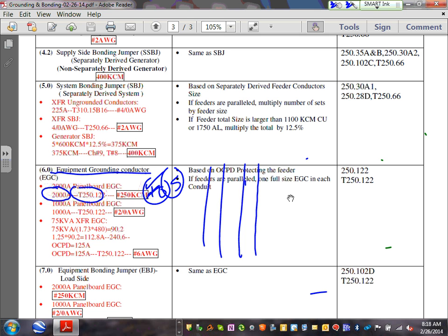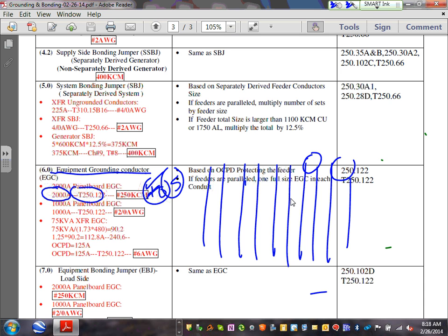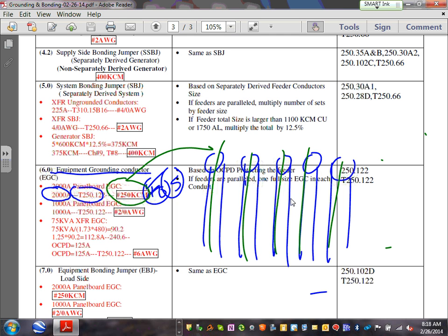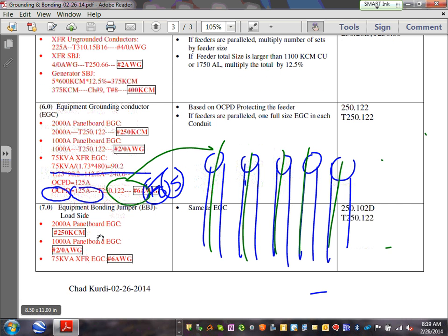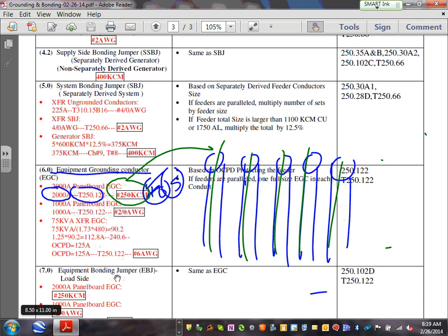Here's 1, 2, 3, 4, 5 conduits. All these are different conduits, and you will be pulling, gentlemen, 1, 2, 3, 4, 5 conductors, one in each and every one of these conduits. Any comments, any questions, guys, about the equipment grounding conductor? Make sense? Cool. So right underneath it, guys, it's called equipment bonding jumper load side.